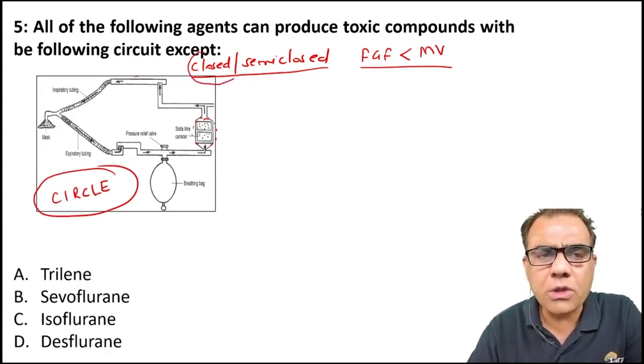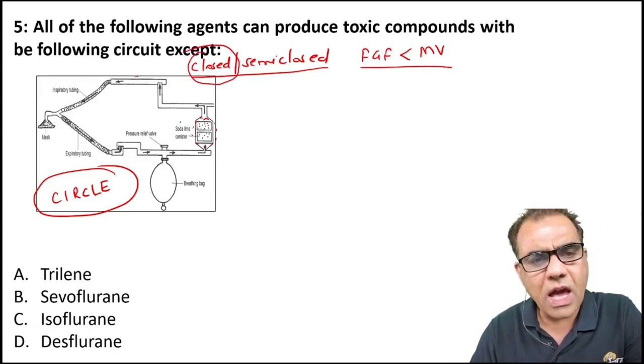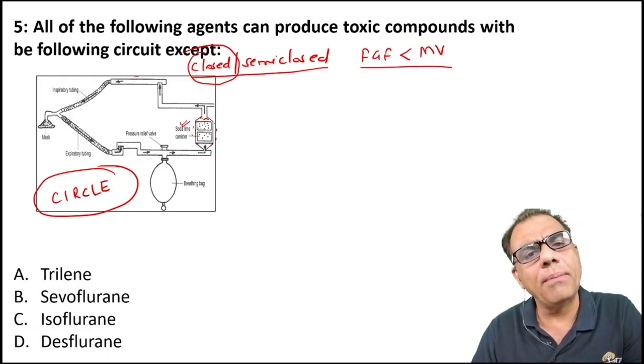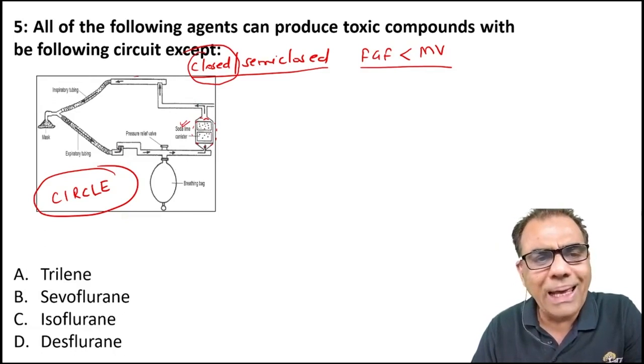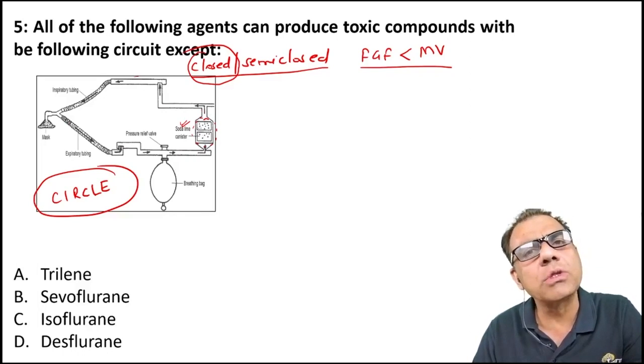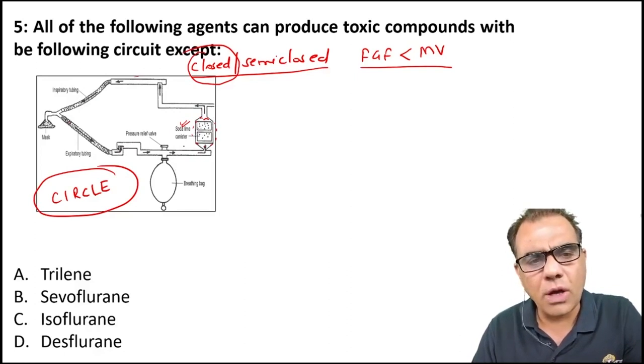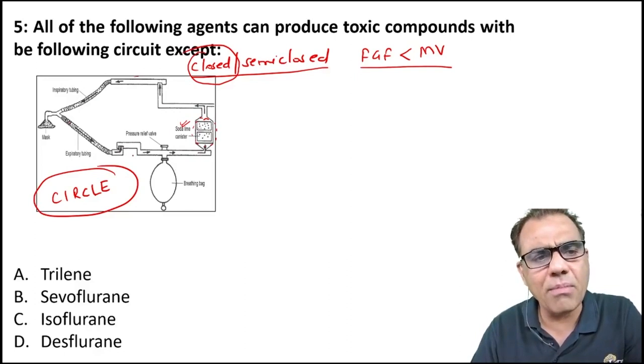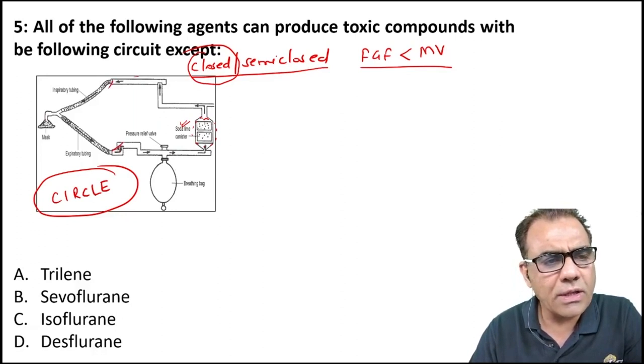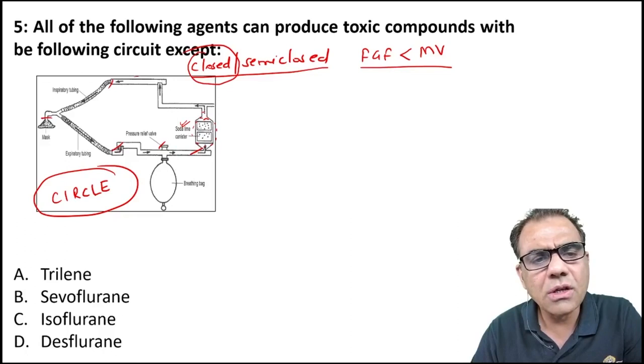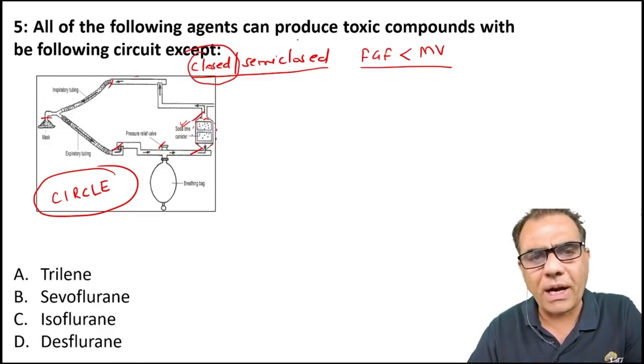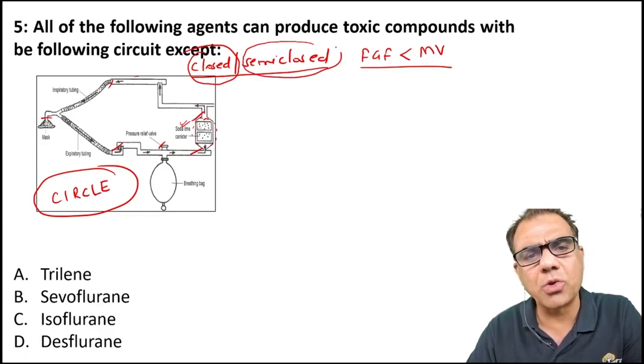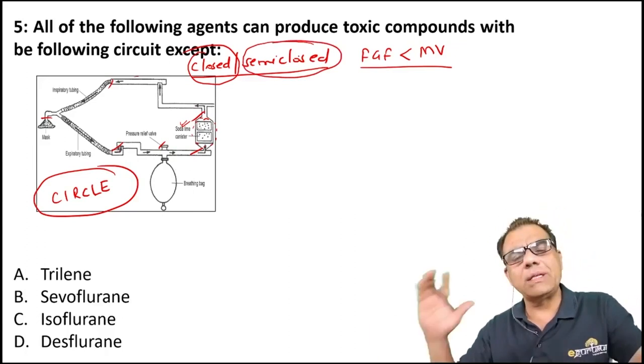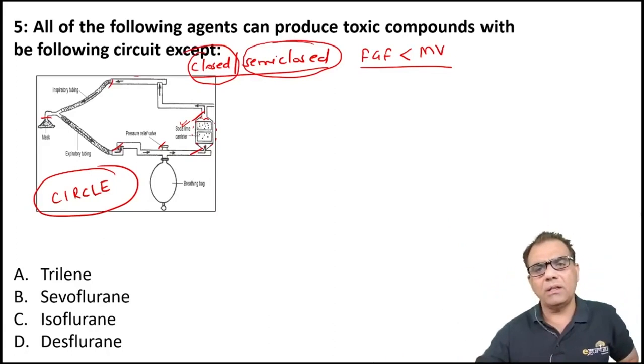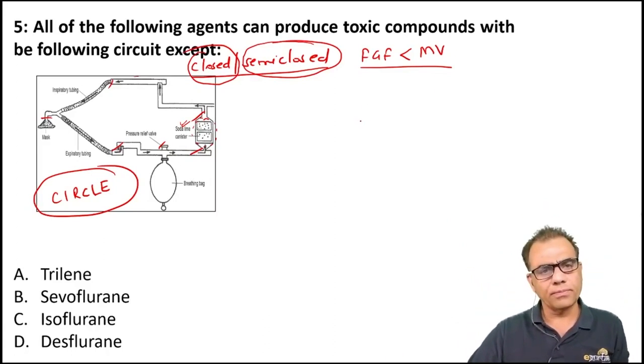We will say it is closed if the gases are completely absorbed by soda bicarb and after soda bicarb absorption the same gases can be completely reused. That's not possible. Soda bicarb is not always 100% effective, and there are many joints you can see where there is a possibility of leakage. So some gases will be leaked. So practically, all these closed circuits we are using are actually semi-closed. So closed is just, you can say, a theoretical concept. But still the fresh gas flow requirement is less than minute volume.